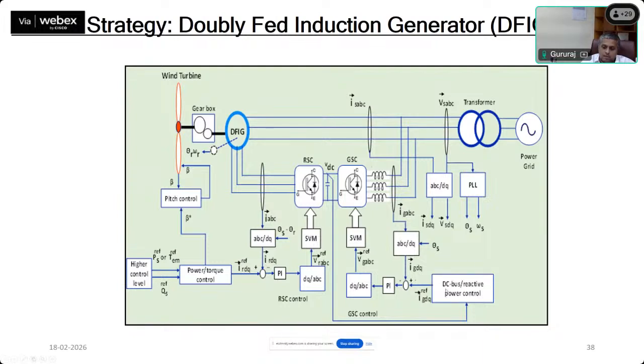There's also an outer voltage bus control loop, so this dual control loop works together to maintain the DC link voltage constant and support the rotor side converter during both subsynchronous and super synchronous modes of operation.